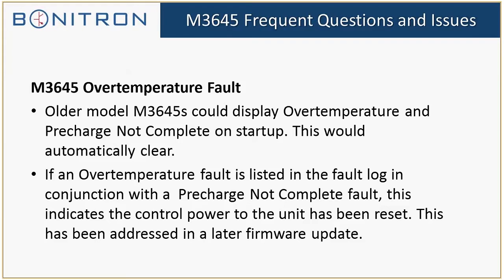The only other issue we have with the 3645 is that just older programs, older software would display a certain fault when the units would start up. Basically, would display an overtemperature fault and a pre-charge not complete on startup. This would automatically clear after a few seconds once the M3645 had completed its own pre-charge. However, customers would see this and not really understand and call in with a lot of problems. This has been addressed in the firmware update, but if I do encounter an older unit, this might be a problem, and this is more just a customer communication issue. We do represent it in the manual, but basically, if you see an overtemperature fault, the pre-charge not complete fault, it's basically a non-issue. It's just a startup.